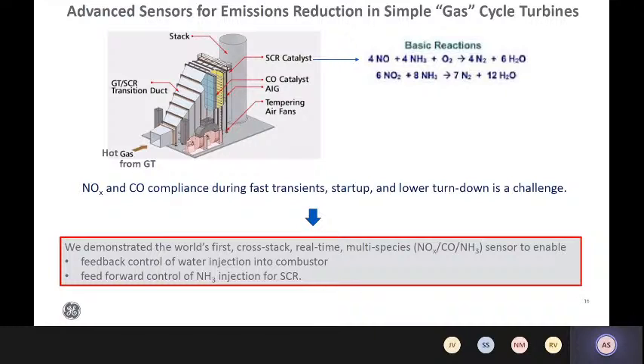Now, it's very hard to figure out how much water you must inject. And this is where there's a lot of need for advanced sensing technologies that can basically detect the amount of NOx that is coming out of the turbine on a real-time basis, and then use that NOx signal to inject just the right amount of water into the turbine, so that you can keep the NOx at the required low levels as required by the regulations.